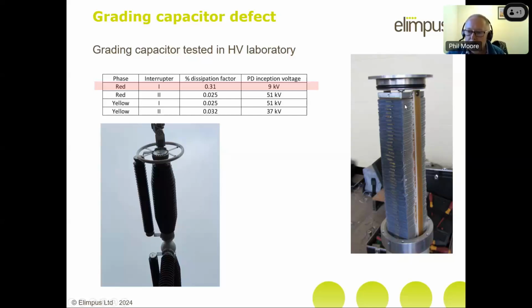But the grading capacitor, if you've never seen one, looks like this. It is actually about 200 individual capacitors all connected in series, and each individual capacitor looks a little bit like, for lack of a better description, a Dairylea cheese slice. It's maybe a 50mm square piece of plastic, and what it is is two bits of aluminium foil, with a mylar plastic sheet separating them, top, bottom and in the middle, which is then folded over itself time and time again until it looks like a Dairylea slice.